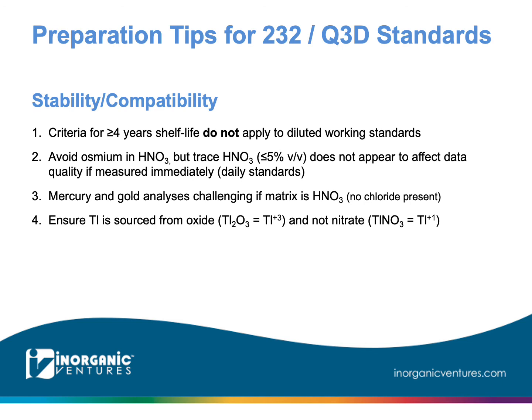Lastly, we just want to point out that if you are preparing your own mixtures and you need to analyze thallium as part of the Class 2B elements, please just make sure that your starting material ensures that thallium is in the +3 oxidation state, or precipitation as a chloride salt can occur, particularly if the precious metals are part of your analysis. Simply put, thallium will behave just like silver if it is in a +1 oxidation state, and you can run into problems if you're measuring the 2B elements such as osmium and the precious metals and you want to include thallium as part of that measurement.